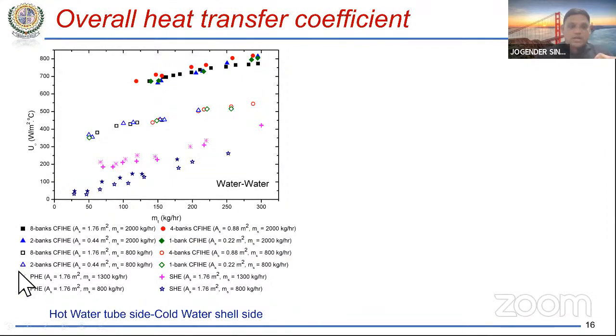So this blue triangle with this blue star here, you can see that this coiled flow inverter with the same heat transfer area is giving very high heat transfer performance. However, here you see the area is very less as compared to the PHE here. And of course, SHE is less than the PHE itself, because PHE has a much higher heat transfer surface area, I mean higher heat transfer coefficient, which is very much proved in the books. So even our device is better than the PHE.